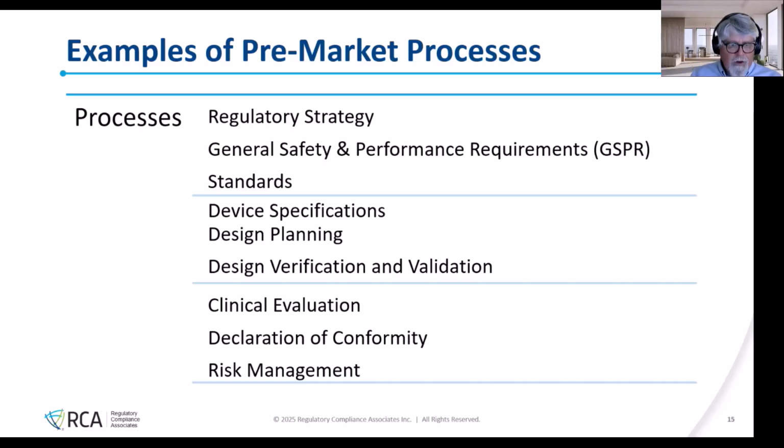And then you're going to have this declaration of conformity. And so what you're declaring here is really important. The declaration of conformity is you're declaring that you meet the regulations, the applicable regulations. But more importantly, this is a piece of paper, or a statement, that you guys or organizations are going to create. Technically speaking, that declaration of conformity is, yeah, you meet the applicable requirements, but you have sufficient clinical evidence to meet the general safety performance requirements that you check that, yeah, you have to meet those.